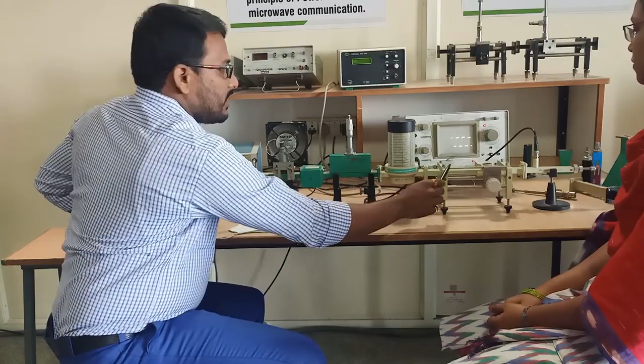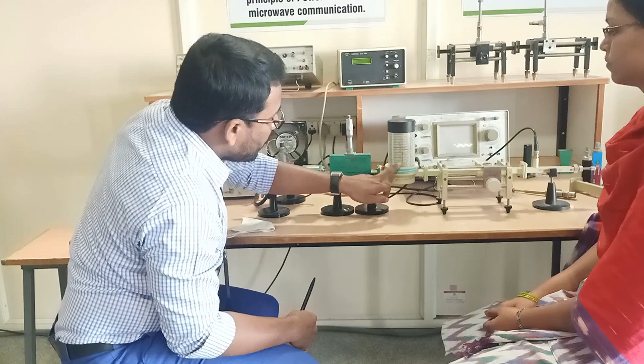By rotating the frequency meter, see, this is the frequency meter. By rotating the frequency meter, you have to fix a particular frequency for the microwave energy generated by the klystron mount. When you rotate it, you will find a dip. This is the required frequency within the band value of 8.2 to 12.4.